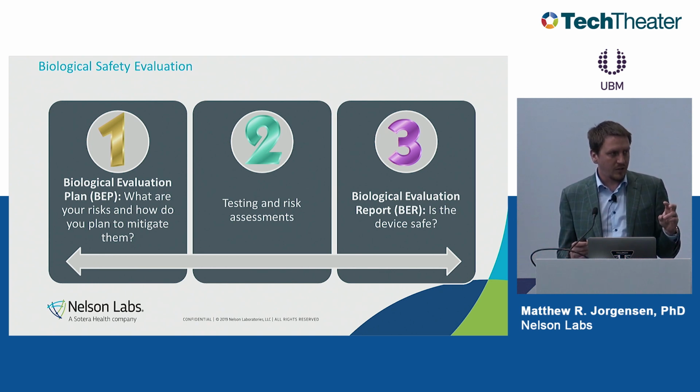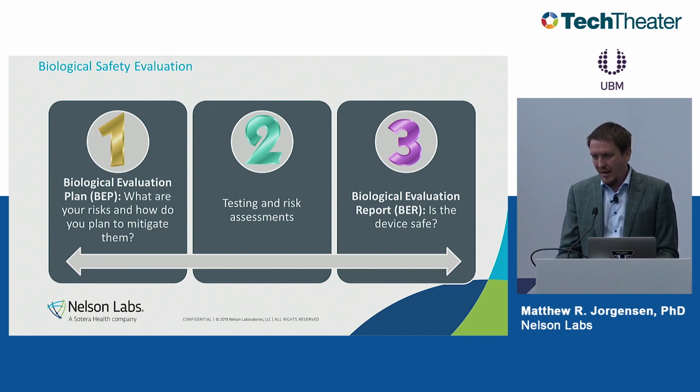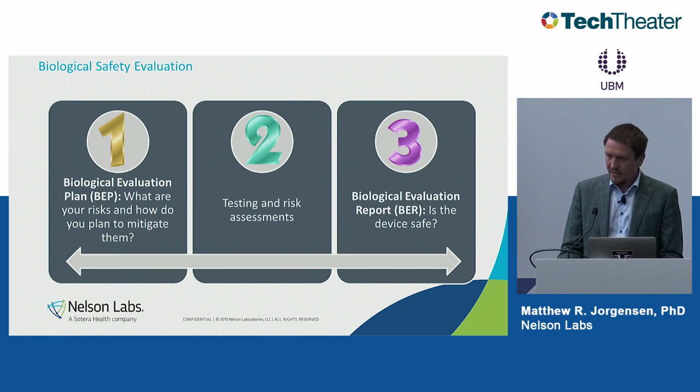So this so-called biological evaluation plan, not only is it a very, very good idea, but it's now required, right? So in 10993-1, it requires that you have a biological evaluation plan, and if you submit to the FDA and you have this nice, wonderful docket of information for your 510K, and you don't have a biological evaluation plan, then there's a good chance that it will get kicked back. So you must start with a plan that demonstrates that you understand the materials and the processing that goes into your device and what risks those are.